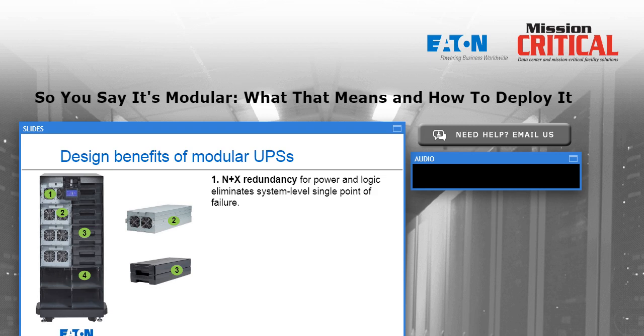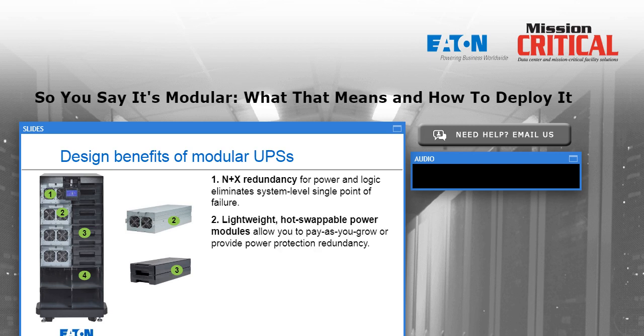So this allows, in addition to capacity adjustment, N+1 or even N+X redundancy. So I can have an N+1 redundant system simply by sliding in one more of those power modules than I actually have to support the critical load. So this eliminates the need to have a separate UPS with a separate battery system and switchgear to tie them all together just to get that traditional N+1 redundancy that so many of our clients desire in the UPS system.